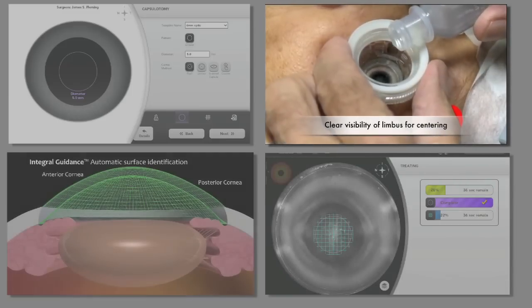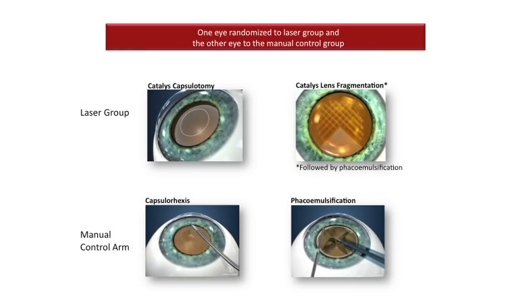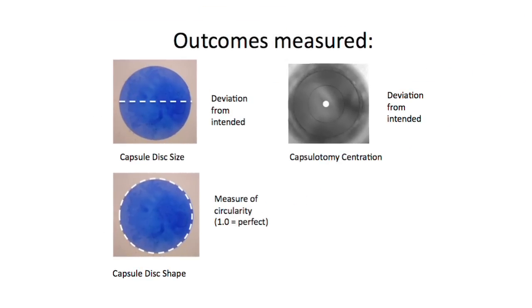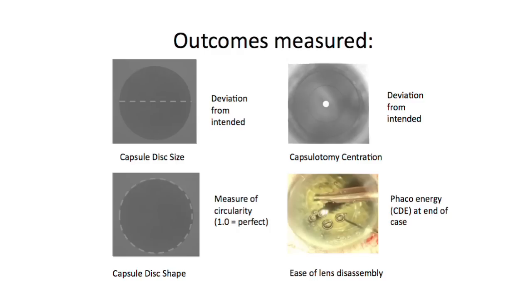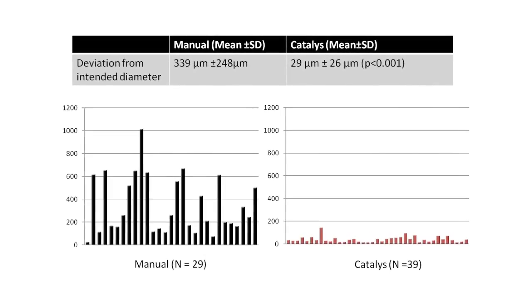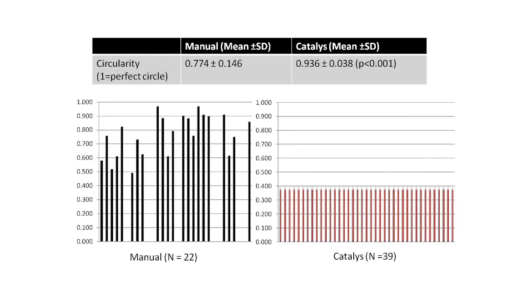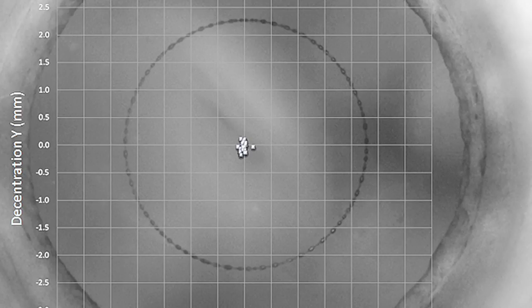The combination of the liquid optics interface, integral guidance's automatic surface detection, and the state-of-the-art laser resulted in unsurpassed clinical data in the prospective randomized study Optimedica conducted. This study evaluated the precision and accuracy of the laser capsulotomy and the ease of removal of femtosecond laser pre-treated nuclear cataracts. Capsulotomies created by Catalys were just 29 microns from the intended diameter, a more than 10-fold improvement over the manual group. Circularity also showed a highly significant improvement. Finally, the laser capsulotomies were centered within 77 microns of the dilated pupil center.